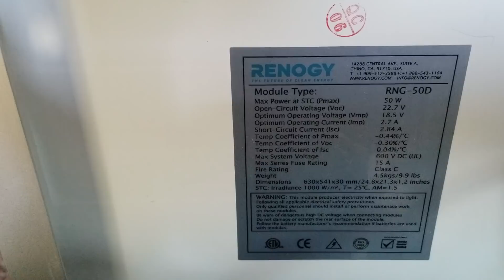Now I'm going to tell you about your PV connection. The caution about this, make sure before you connect to a PV module, please install a separate DC circuit breaker, not an AC circuit breaker. Make sure you're able to cut off the power coming from your panels before it enters the inverter. You need a DC circuit breaker between the inverter and the PV modules. So you have to have that.